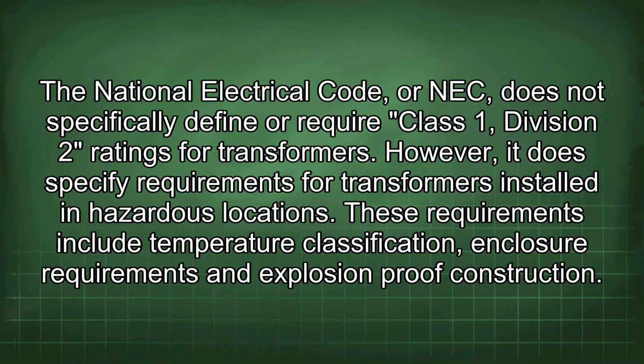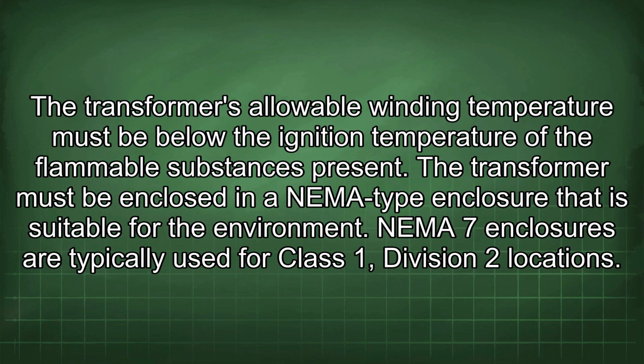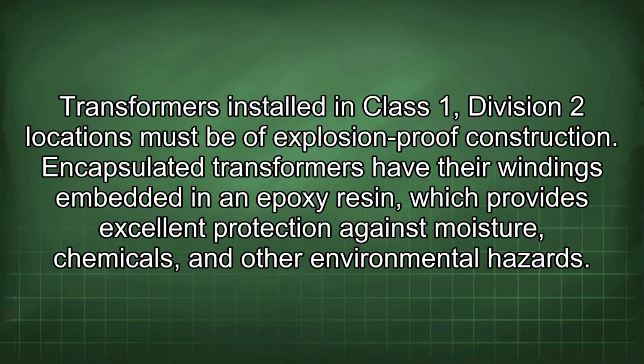These requirements include temperature classification, enclosure requirements, and explosion-proof construction. The transformer's allowable winding temperature must be below the ignition temperature of the flammable substances present. The transformer must be enclosed in a NEMA-type enclosure that is suitable for the environment. NEMA 7 enclosures are typically used for Class 1 Division 2 locations. Transformers installed in Class 1 Division 2 locations must be of explosion-proof construction.